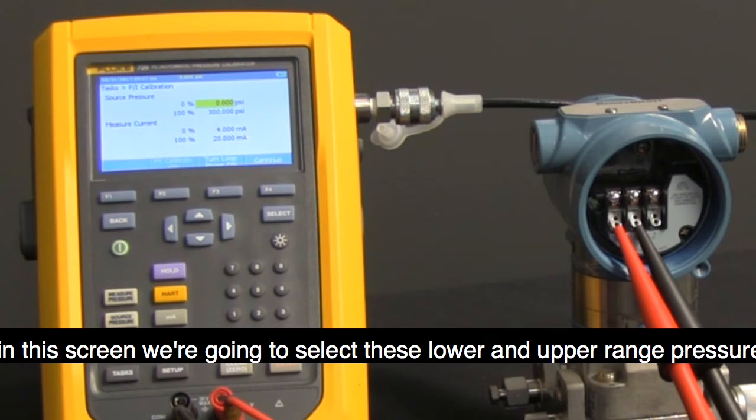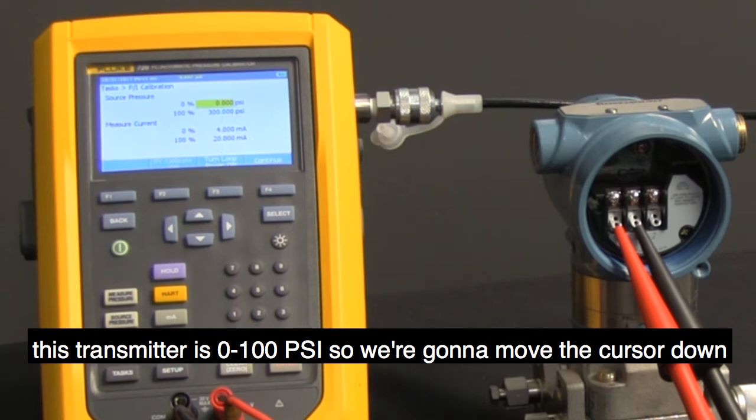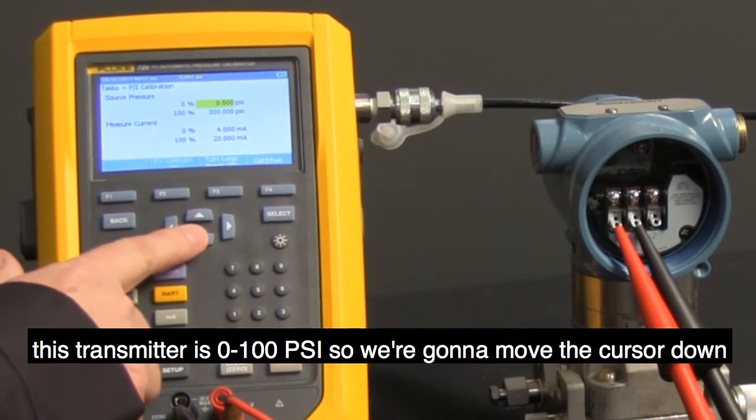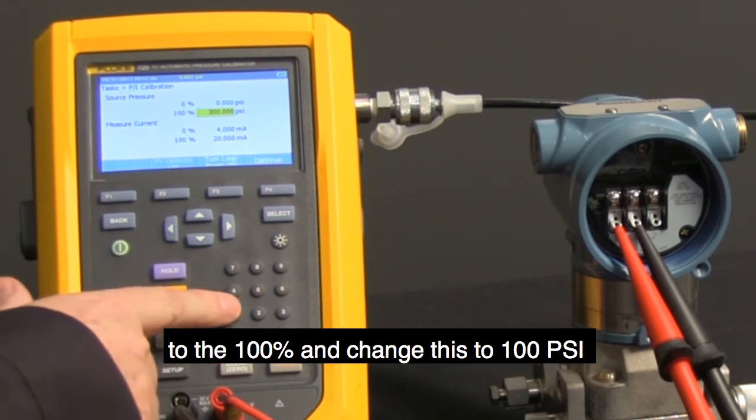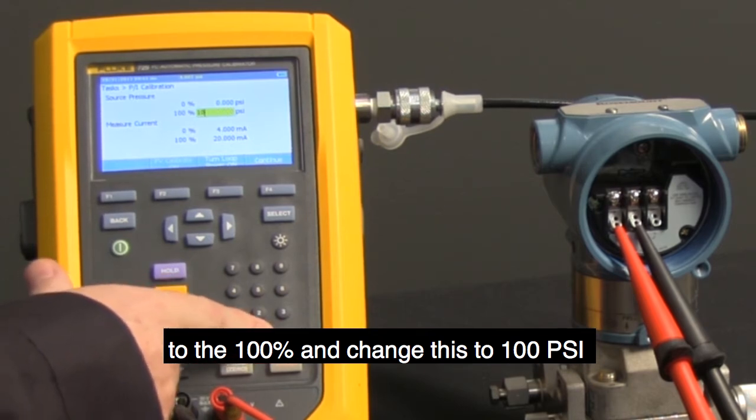In this screen, we're going to select the lower and upper range pressure. This transmitter is 0 to 100 PSI, so we're going to move the cursor down to the 100% and change this to 100 PSI.